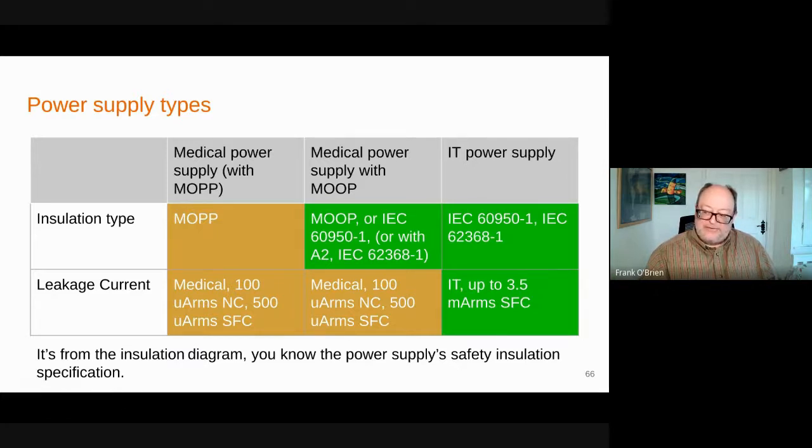So this could be a gotcha. You can't just buy this guy and think he's giving you this. But if you were careful about what you're specifying, can you give me this power supply, but you might have to change the inlet, the EMI filter. Do you know what I'm talking about? Can you give me that? Oh, yeah, I know exactly what you need. Good, here it is.